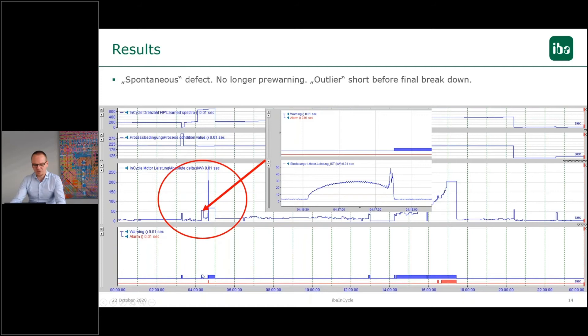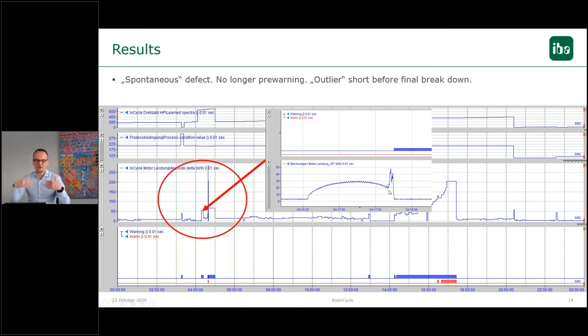We can detect this before the big issue happens — we were able to give out a warning, and we saw in the curve or in the cycle that at this position there quite likely was a breakage of a tooth. So we can directly warn on this event.